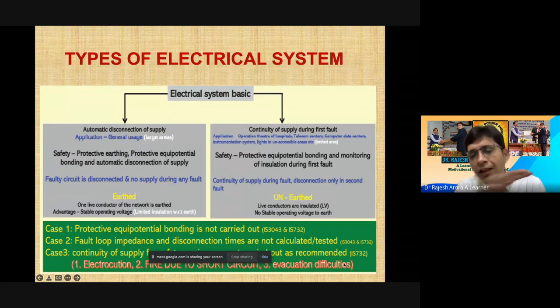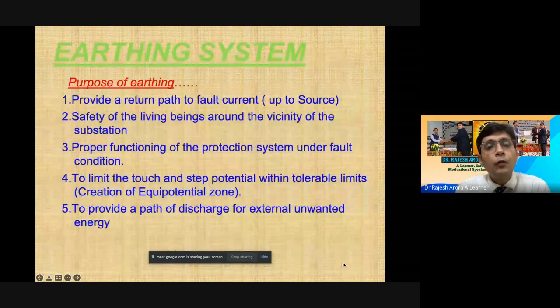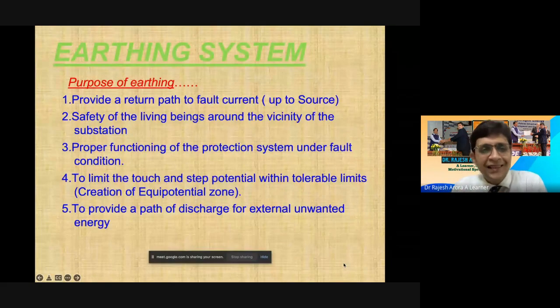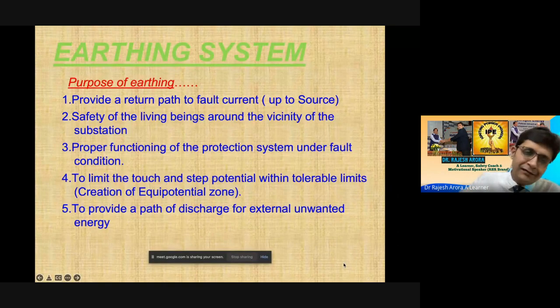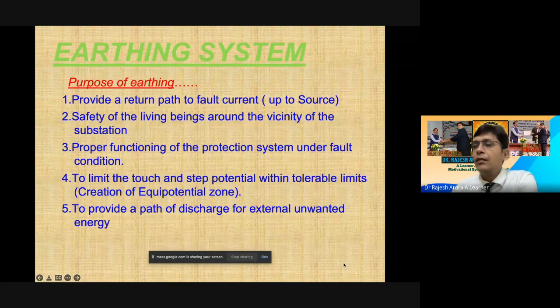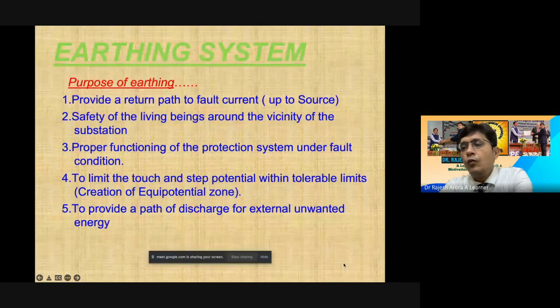We always talk about earthing and IS 732. We must have a good overcurrent protective device, we have to have that ELCB. And to understand that system further, we have to understand the earthing. Why do we need earthing? The reasons, the answer.